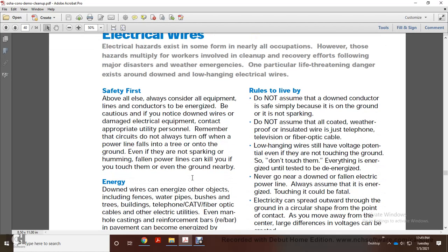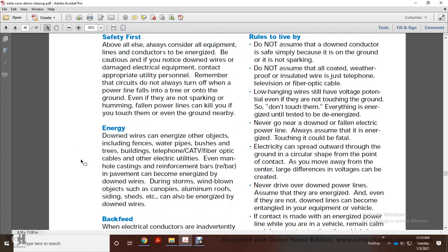Safety first. Above all else, always consider all equipment and line conductors to be energized. Be cautious if you notice downed wires or damaged electrical equipment, and contact the appropriate utility personnel. Remember, these circuits do not always turn off when a power line falls into a tree or onto the ground. Even if they're not sparking or humming, fallen power lines can kill you, and they can energize even the ground nearby. Downed wires can energize other objects, including fences, water pipes, bushes, trees, buildings, telephones, CATV, fiber optic cables, and other electrical utilities.